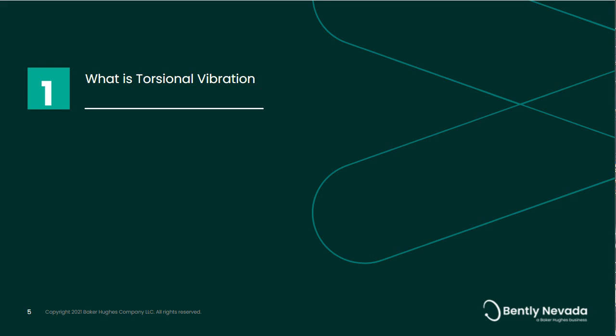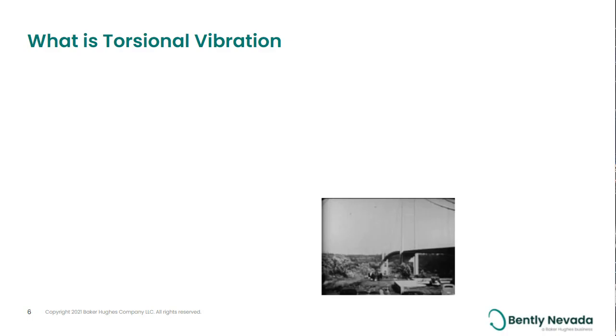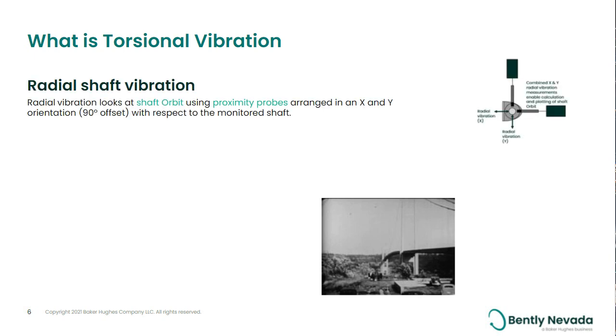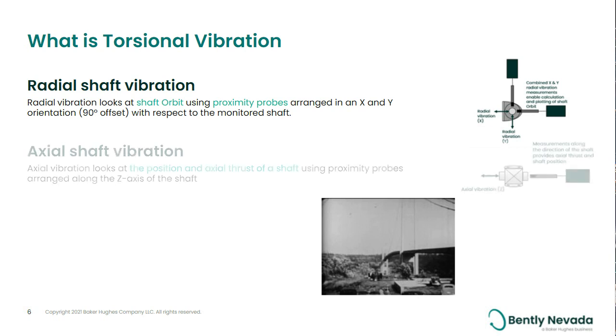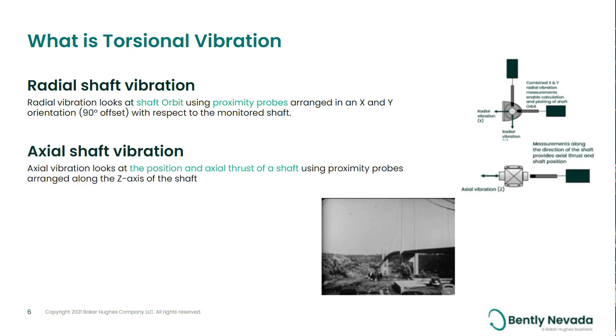Torsional vibration. Let's first define the basics. In the vibration world, one of the key vibrations that most folks are familiar with is certainly radial shaft vibration. This is leveraging traditionally proximity probes in an XY or 90-degree offset to monitor a shaft's radial vibration. The next key vibration component is axial, and this is again taking a proximity measurement, this time looking at the actual thrust, typically along the Z-axis of the shaft.